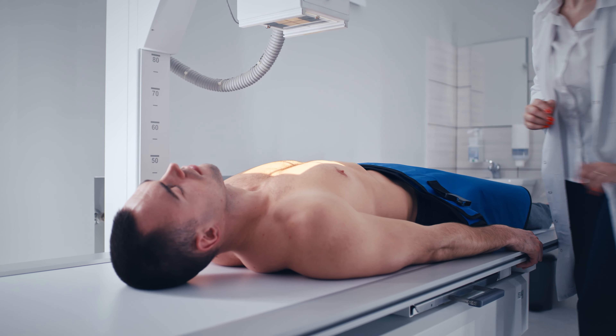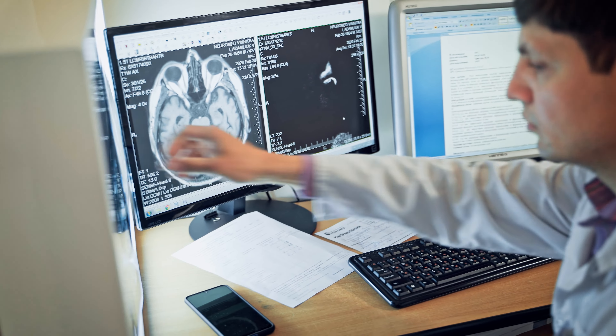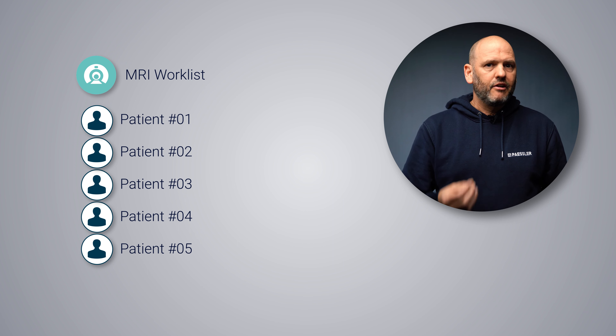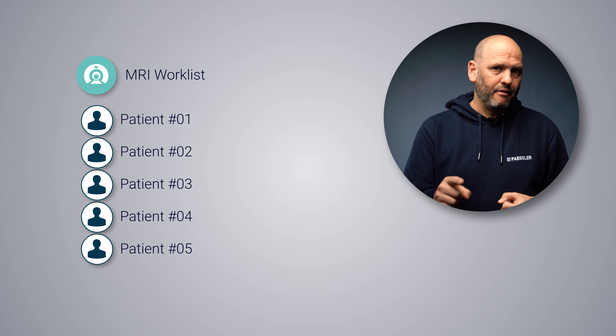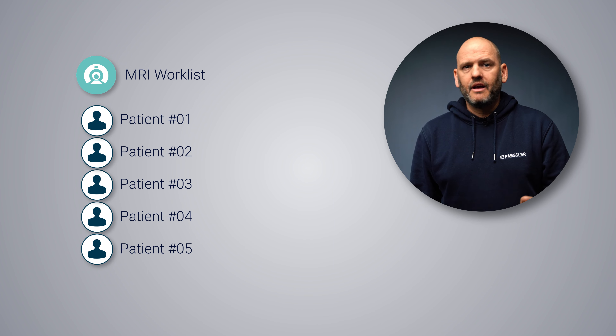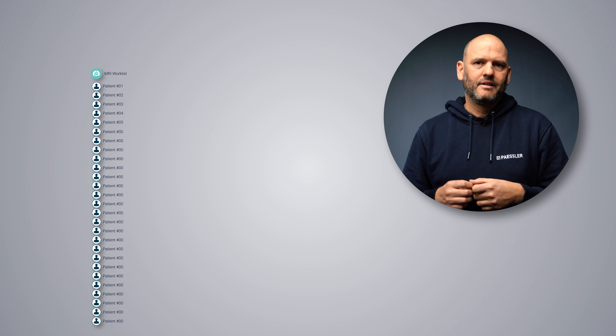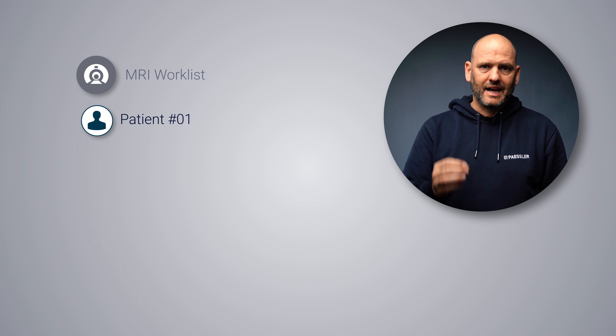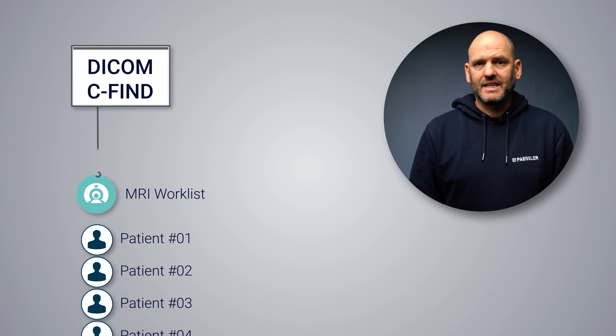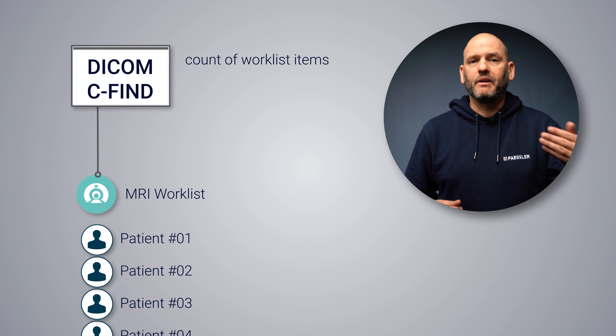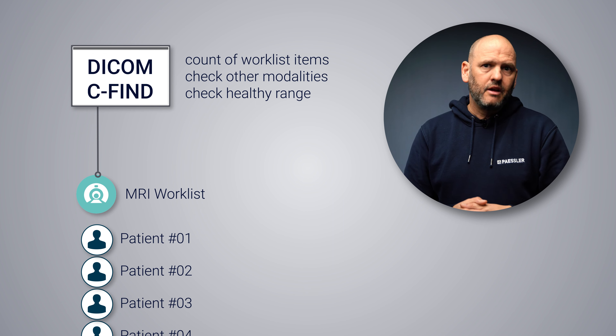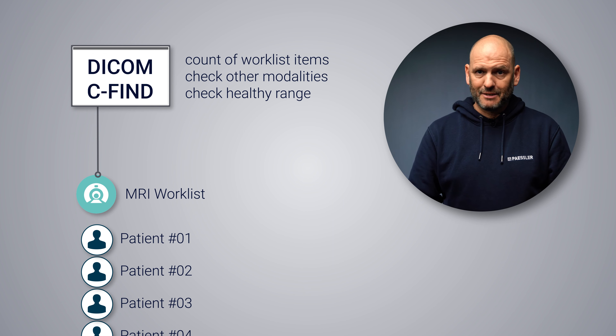Another DICOM request is C-FIND. Modalities have a worklist attached to them — basically a list of jobs that the modality has to process. If five patients need an MRI scan, the modality has five worklist items. The number of worklist items currently associated with the modality is a good indicator of that modality's health. If the modality has a bottleneck or malfunction, the number of items in the worklist might grow disproportionately. If the count is too low, it could mean requests are not being processed. You can use DICOM's C-FIND request to count the worklist items for a specific modality or across all modalities, and spot problems if the count goes higher or lower than expected.